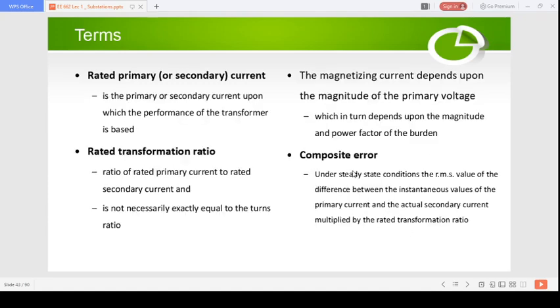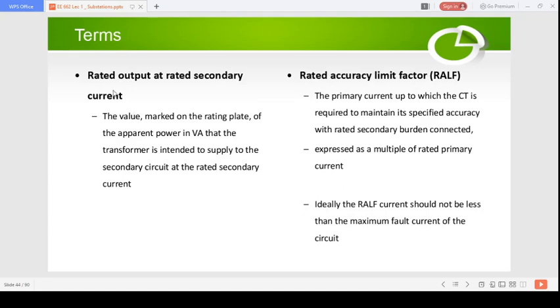Okay, so that's how the composite error is defined. The rated output at rated secondary current is defined as the value marked on the rating plate of the apparent power in VA that the transformer is intended to supply to the secondary circuit at the rated secondary current. So this rated output at rated secondary current is marked on the transformer plate. So this is the apparent power that the transformer is intended to supply to the secondary circuit at the rated secondary current.